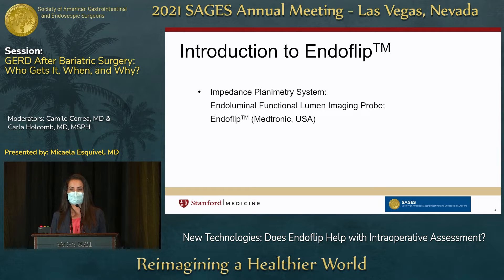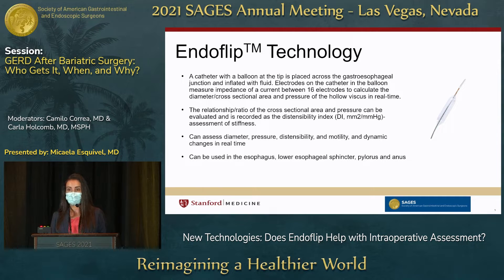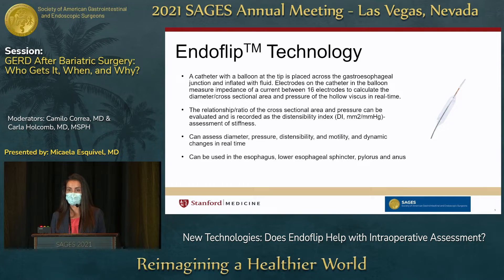Endoflip is an endoluminal functional lumen imaging probe — an impedance planimetry system. As you can see from this image on the right, it's a catheter with a balloon at the tip that, for our purposes, would be placed across the GE junction and inflated with fluid. Electrodes on the catheter and the balloon measure impedance of a current between 16 electrodes within the catheter. They can calculate the diameter, the cross-sectional area, and the pressure of a hollow viscus in real time.